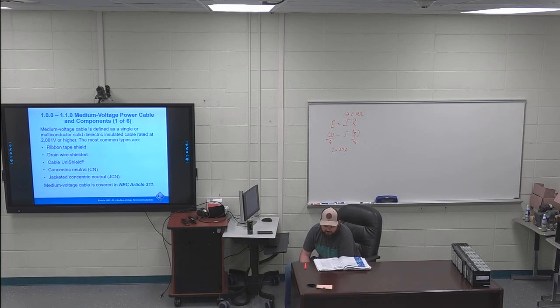Although this conductor has full ampacity ratings, the general rule for sizing is to consider one conductor size smaller than the concentric or compressed cable. This reduced conductor size results in a proportional reduction of all cable layers, a consideration when sizing for molded rubber devices. So that just compacts everything and makes the cable even smaller than either the compressed or the concentric stranding.